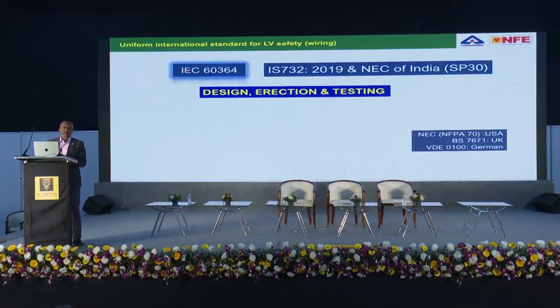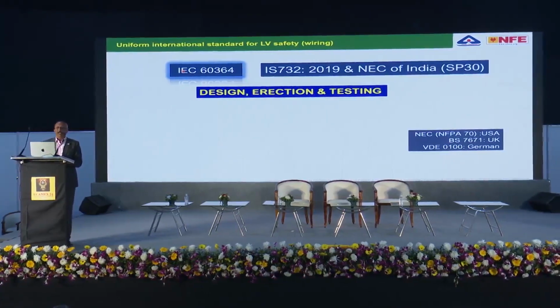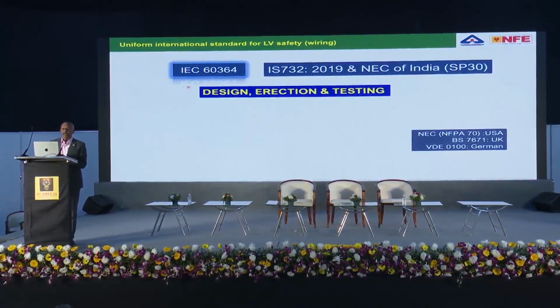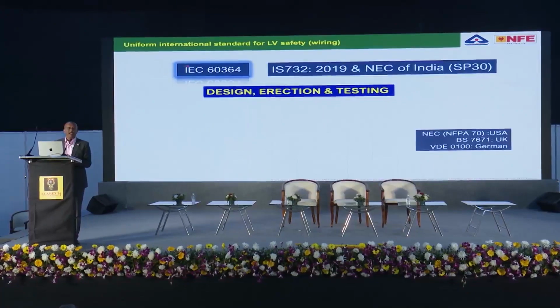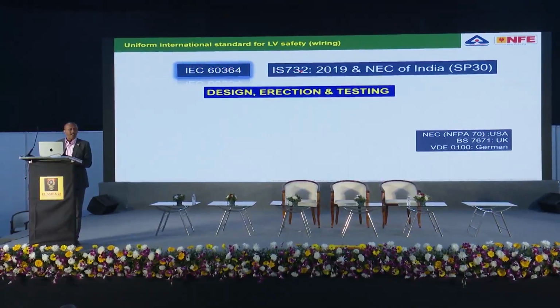Now, what are others doing? Why are the other countries able to make a very good electrical safety scenario, much above us? If we look at low voltage electrical installation, low voltage means up to 1000 volt AC, 1500 volt DC. Globally, all around the world, the same standards are used, made by IEC TC64. The standard is called IEC 60364. In India, the same standard is adopted as IS 732, up to some of the chapters of the same IEC, then NEC. So overall, the entire international standards are followed in America for making safe buildings, followed in UK to make their electrical installation, followed in Germany, France, Italy, all over the globe.